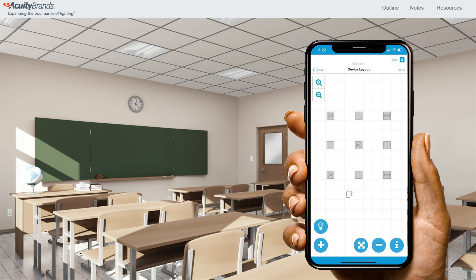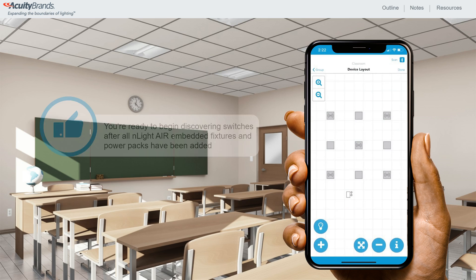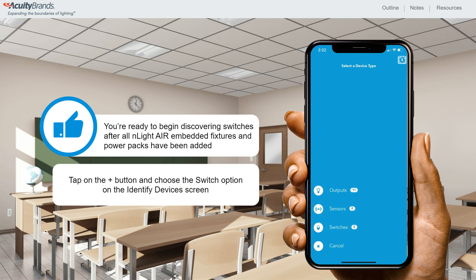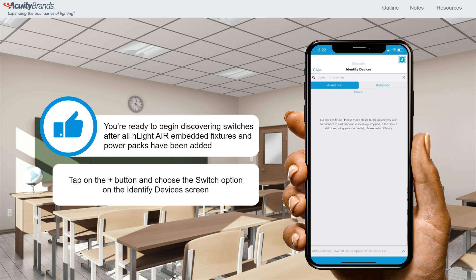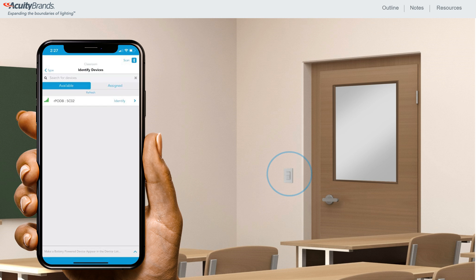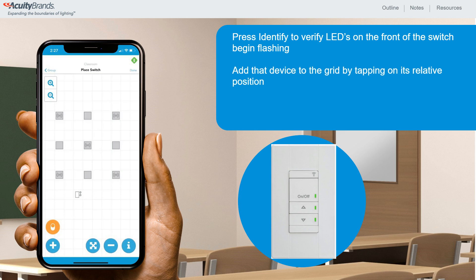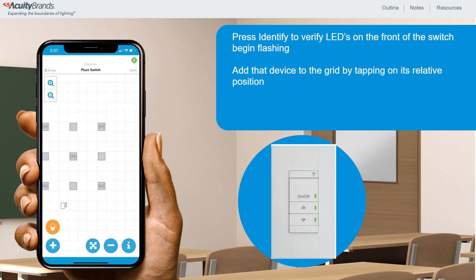Once all nLight AIR embedded fixtures and power packs have been added, you're ready to begin discovering switches to add to the grid. Tap the plus button and choose the switch option on the Identify Devices screen. You may notice that there are zero switches showing up — that's because switches go to sleep after periods of time with no button presses. To wake a switch up, press any button. After the button is pressed, you'll see a wall switch appear on the Identify Devices screen. Press Identify to verify that the LEDs on the front of the switch begin flashing, then drop that device on the grid by tapping on its relative position.